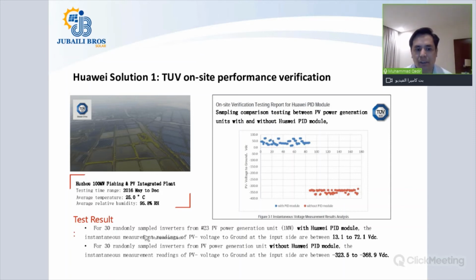So what happened is that for 30 randomly sampled inverters taken from the part where the NT-PID module from Huawei was used, the PV negative voltage to ground was tested, and as the graph shown here, you can see that the PV module negative potential to earth was shifted to the positive side, ranging from 13 to almost 72 volts. On the other hand, in the areas where the NT-PID module was not used, when checked by the TUV guys, the negative potential of the PV string to earth was found between minus 323 to minus 368. And this results in degradation of your PV plant if you have accumulation of positive ions on the surface of your PV panel.